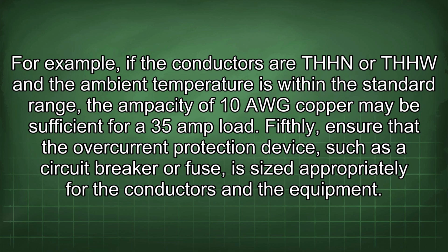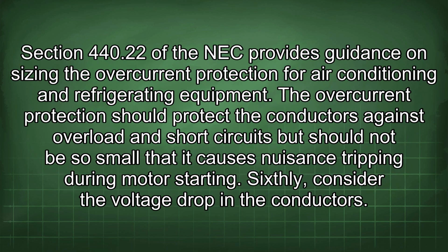Fifthly, ensure that the overcurrent protection device, such as the circuit breaker or fuse, is sized appropriately for the conductors and the equipment. Section 440.22 of the NEC provides guidance on sizing the overcurrent protection for air conditioning and refrigerating equipment. The overcurrent protection should protect the conductors against overload and short circuits, but should not be so small that it causes nuisance tripping during motor starting.